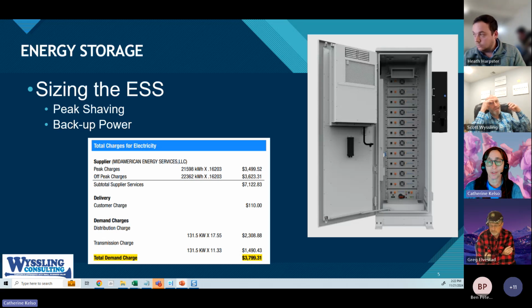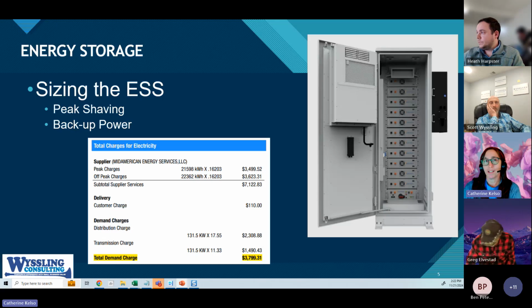You just need a big inverter. But if they're hitting that demand and sustaining it for long periods, you have to worry not only about having a large inverter to cover it, but also about having a lot of kilowatt hours stored in the battery to maintain that high power flow and offset the demand, so they don't hit a demand charge at any point in their billing cycle. That's what you have to look at when sizing batteries for peak shaving.